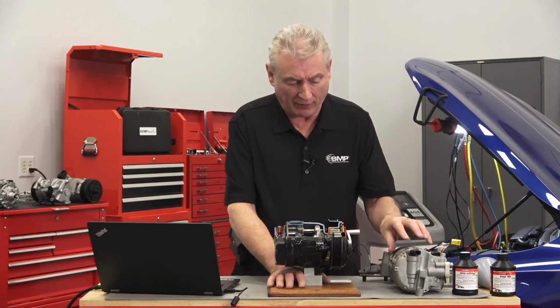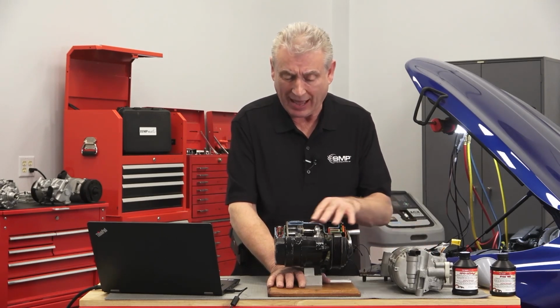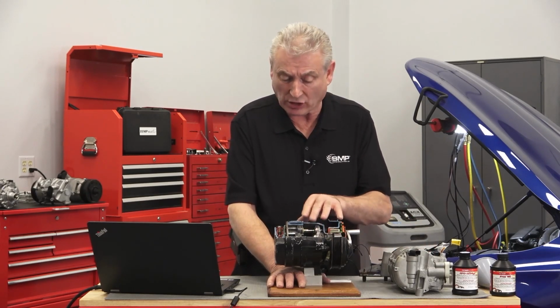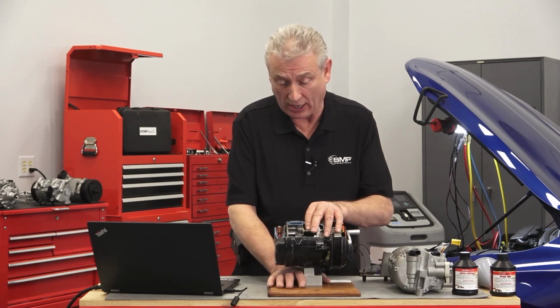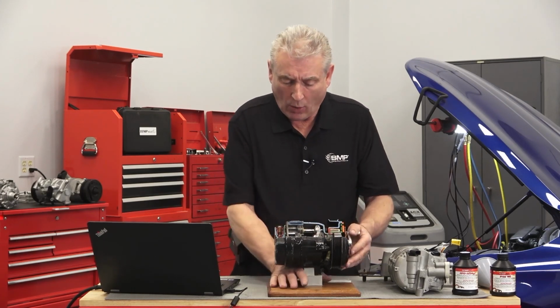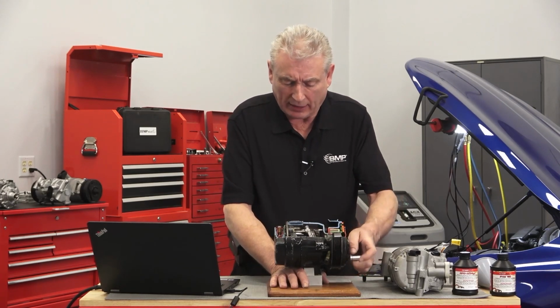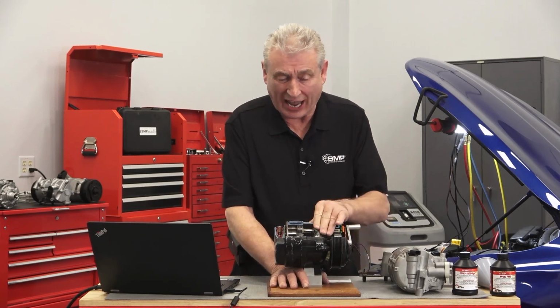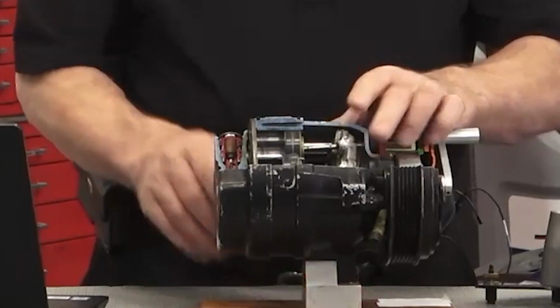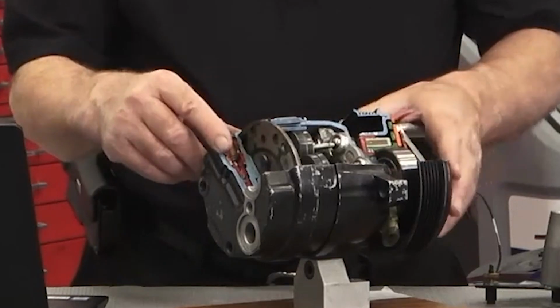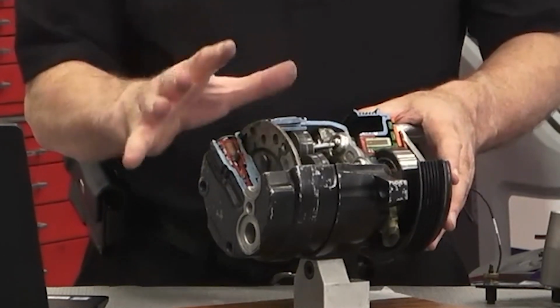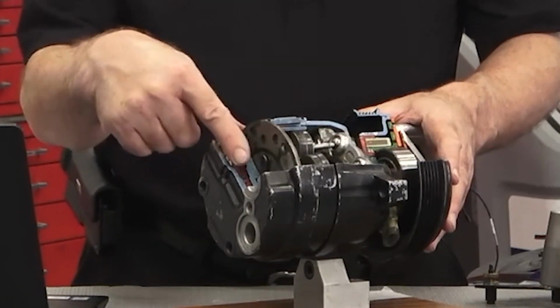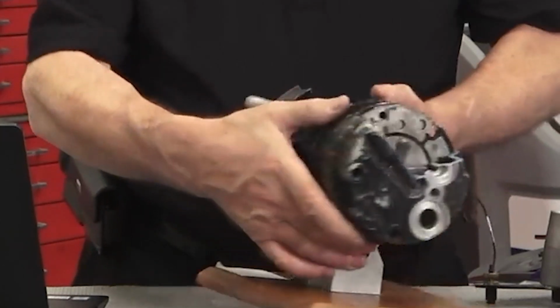That's how, internally, if we look inside one of these compressors, this is actually how it works. It's actually based on a much older technology, if you like. Now, the key thing to understand is how we change the angle of the wobble plate. If you look on the rear head here, I've got a control valve. This is the old school pneumatic control valve. You're probably familiar with this.